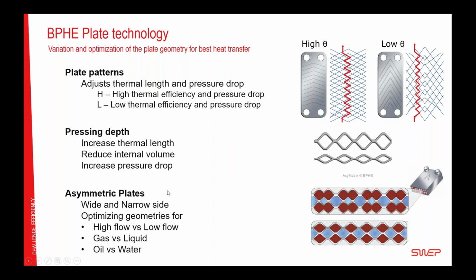And then we come to the asymmetric plates. So what is that? Let's start with a symmetric one. In a symmetric heat exchanger, we combine all this data up here, but the sides do look the same. The cold side and the hot side look exactly the same. There might be H or L type plates, but they look the same. However, in an asymmetric heat exchanger, one side is the thermally long one because it's narrow, and the other side is thermally shorter because it's a wide side. Then you can combine a thermally long or high pressure drop side with a low pressure drop side. When is it needed? Well, if we have a high flow versus low flow side, or gas versus liquid, oil versus water, or similar. In our SSP part, we will give an example of this.